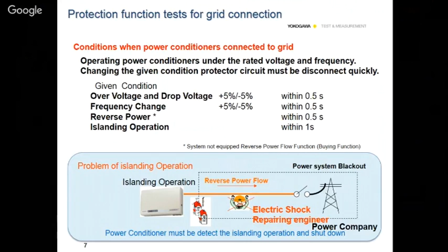How can we use a power analyzer for this protection functional test? Islanding operation is detected by measuring the active power and reactive power, and accurate reactive power must be measured in the harmonics mode. This is a trend display. We have connected a WT3000 for observation of the protection procedure, with a fast update rate of 50 milliseconds and a trend display of voltage, current, power and reactive power. Q is nothing but reactive power, along with frequency, with simultaneous measurement of both normal and harmonics.